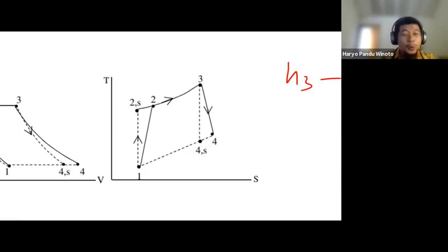When you bought a new gas turbine, the exhaust temperature may be around 400 degrees centigrade. That's good, that's a new one. Then after 1 year, the exhaust temperature is getting bigger, 450. What do you think when you have 450? What happens?